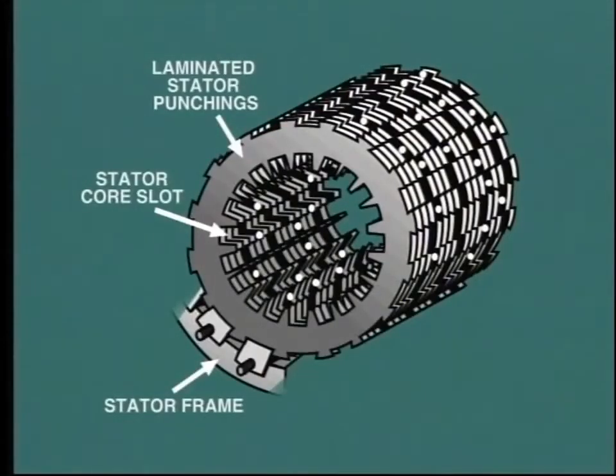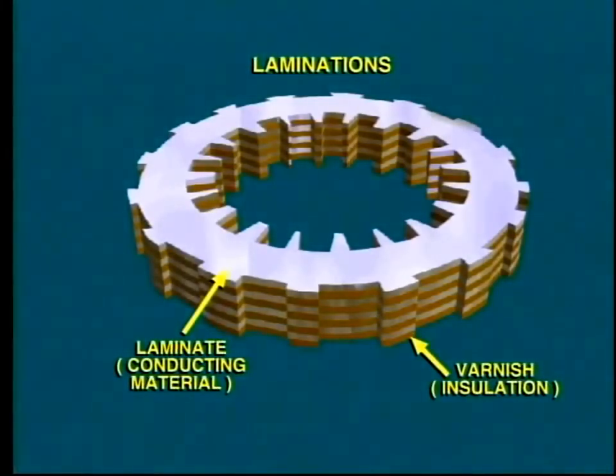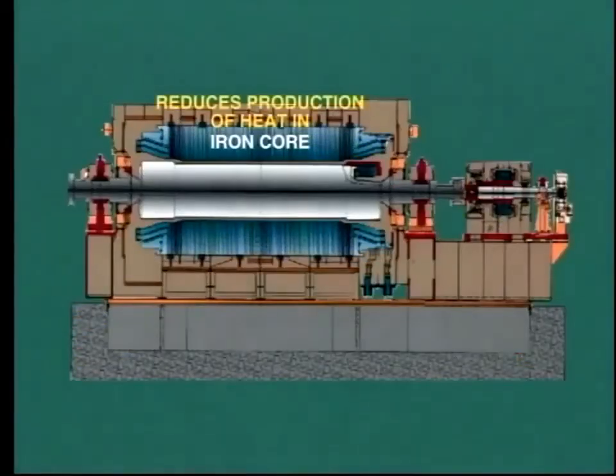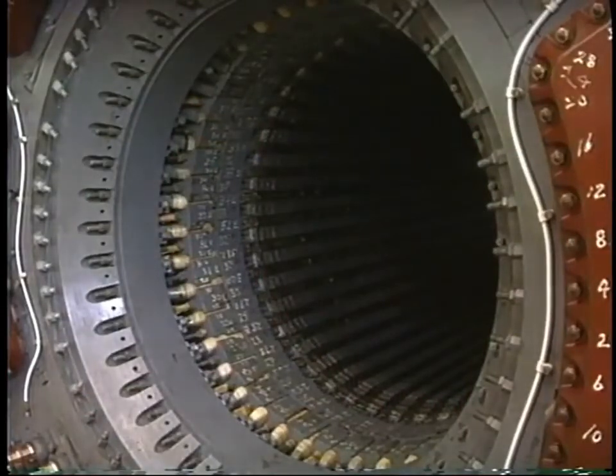The slots run end to end. The iron core is made up of laminations of special steel. Each individual lamination or plate is coated on one side with an insulating material, the objective of which is to reduce the flow of induced eddy currents in the core. This in turn reduces the production of heat in the iron core and thus keeps its temperature down. The laminations are tightly packed together and secured within the stator frame.